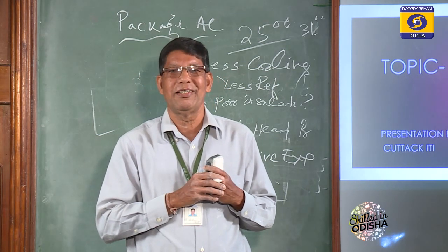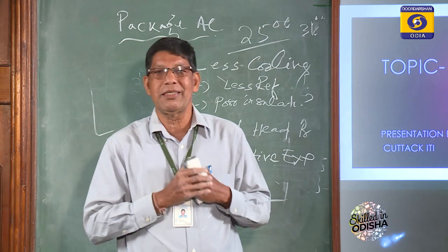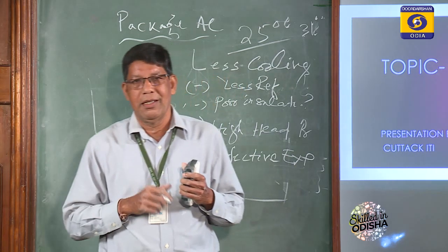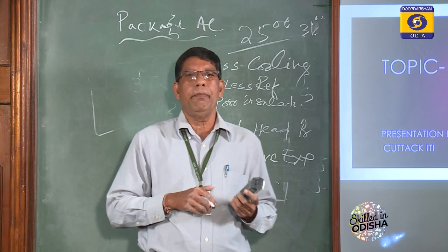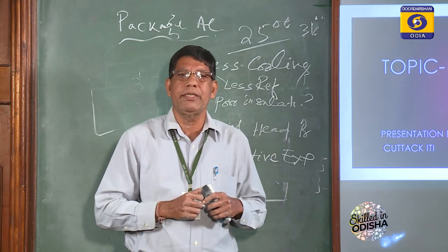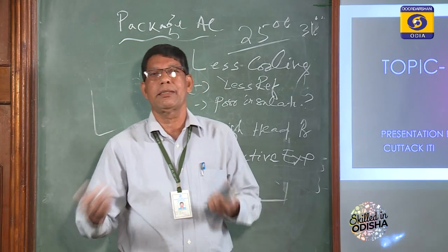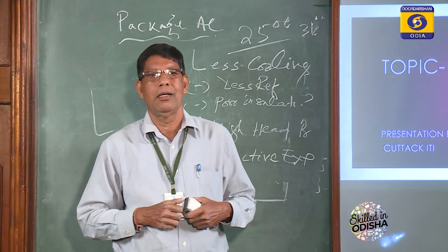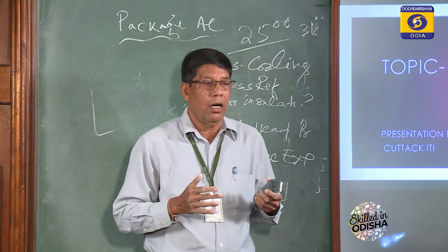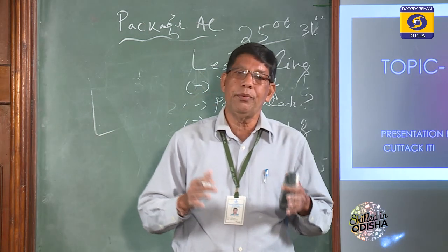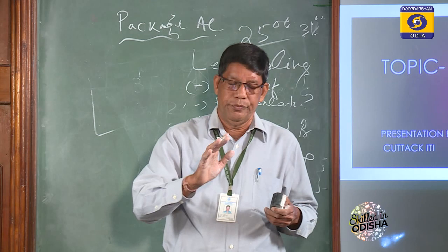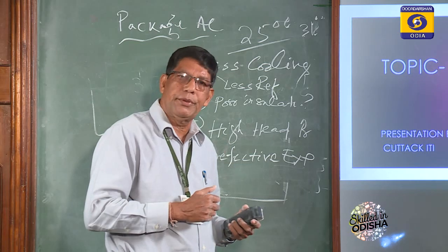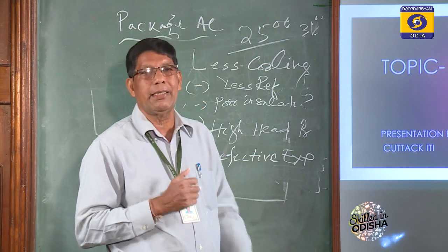A defective thermostat, choking in the system. These are all facts. Then the compressor runs with high pressure. What is high pressure running? Excess charge of refrigerant, less oil. These are all things we have to consider in troubleshooting systems.